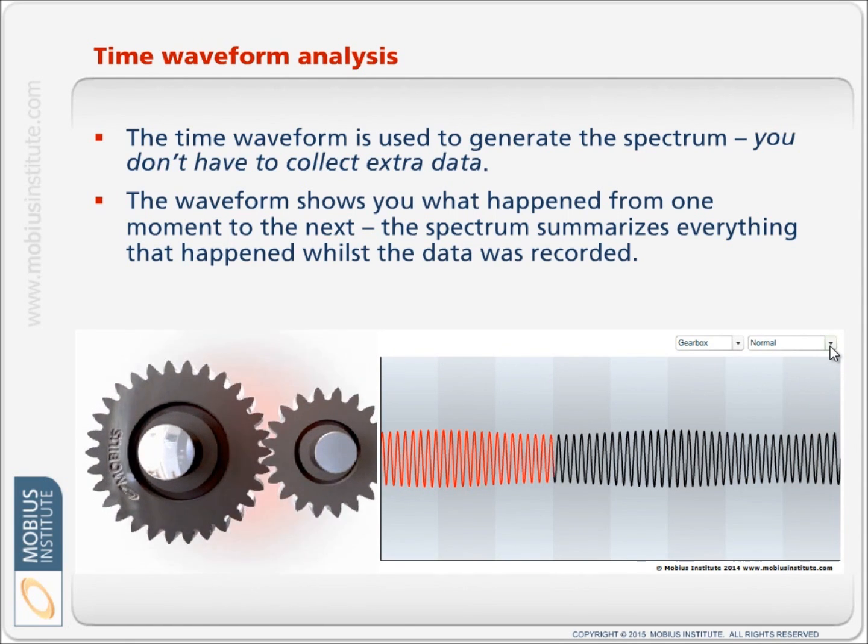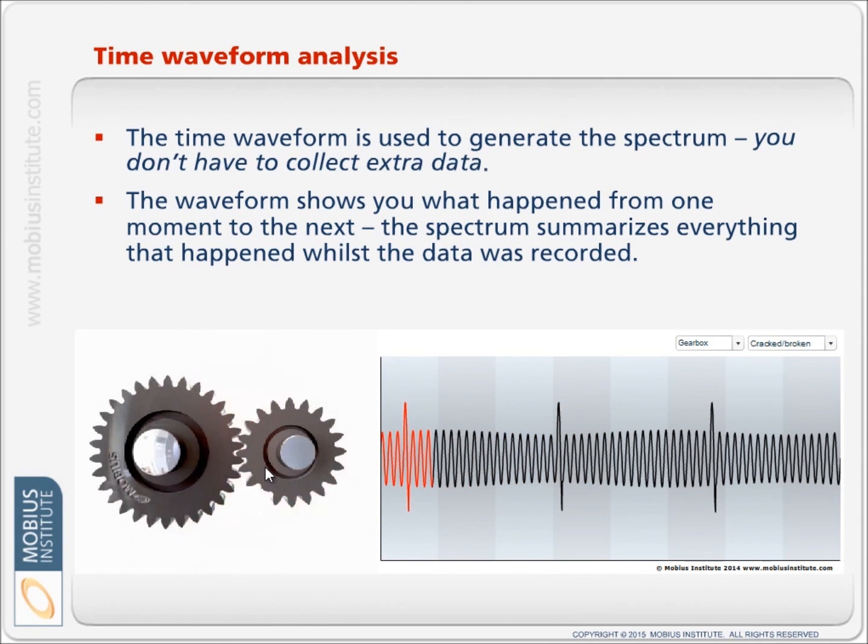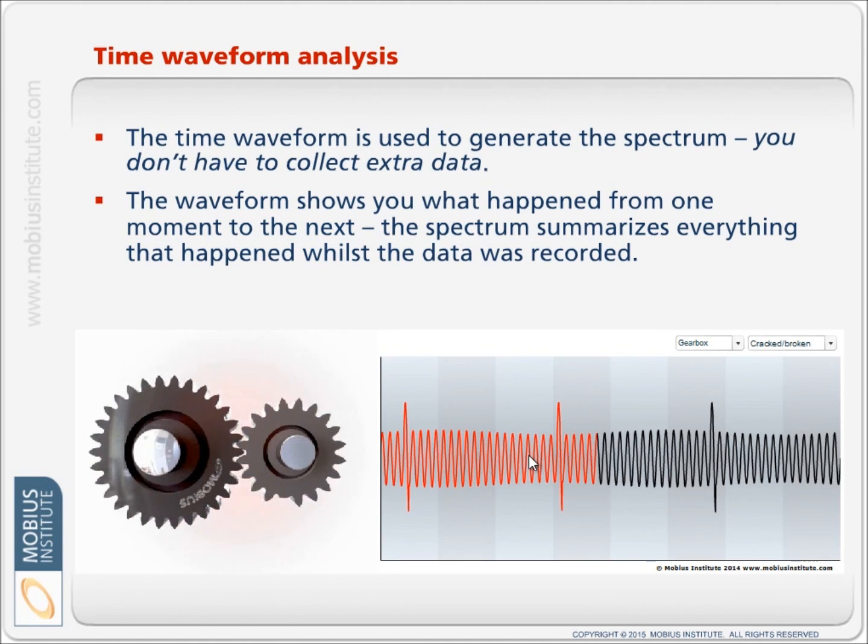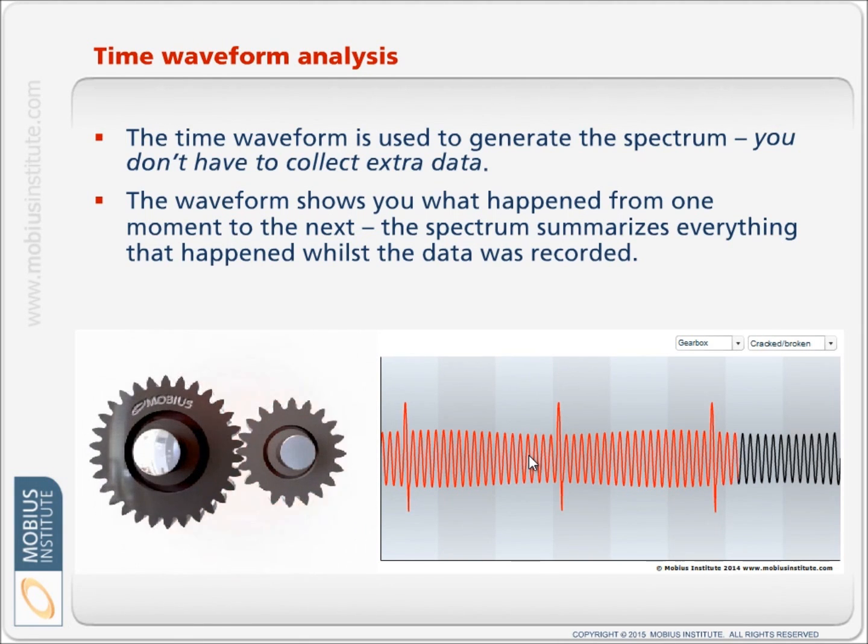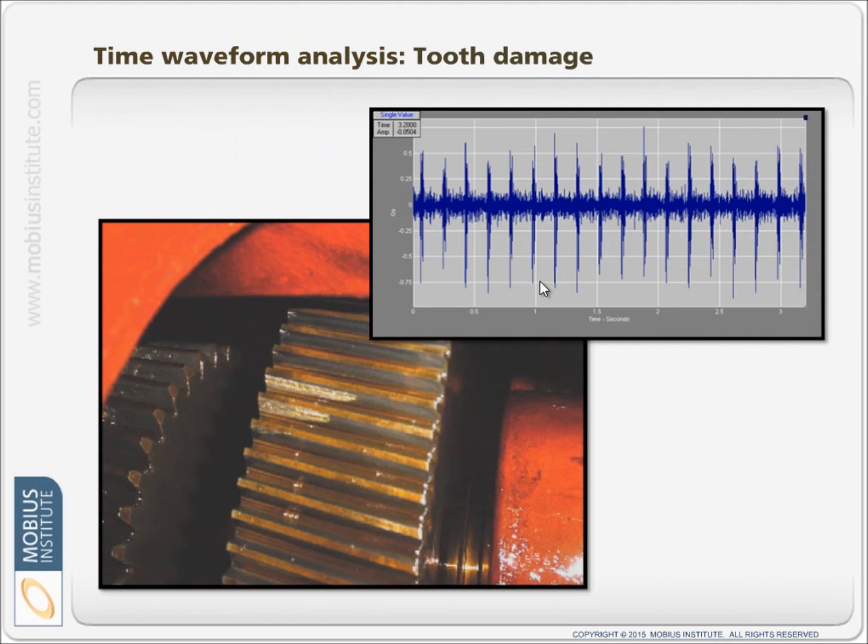Now if there was a problem with the gear, let's say a broken tooth, each time that broken tooth goes through the mesh we get an extra spike. We're not trying to talk about gearbox faults particularly. The point is that the time waveform gives us some information which would be harder to see in a spectrum. It is very clear what is happening in this case, but in a spectrum it is more difficult.